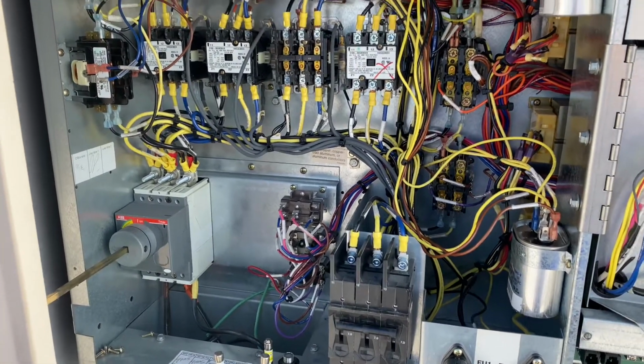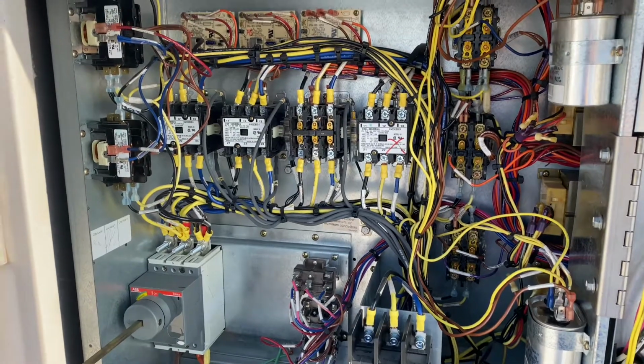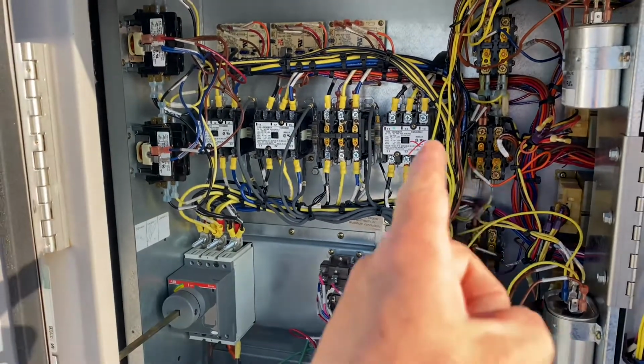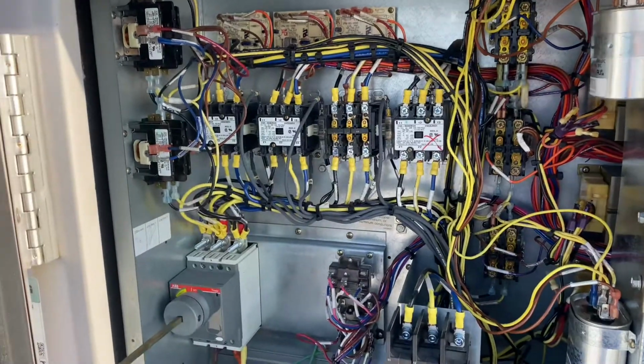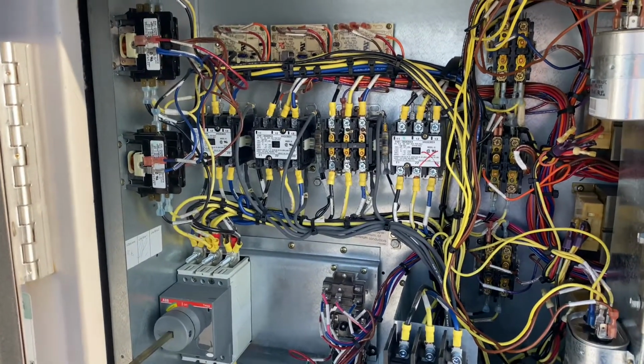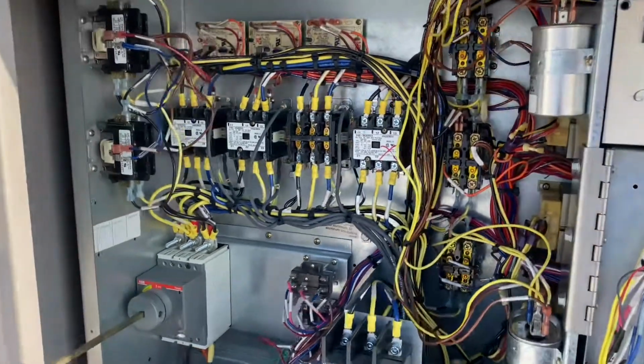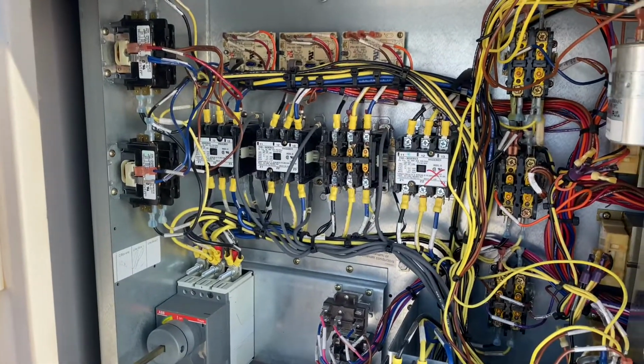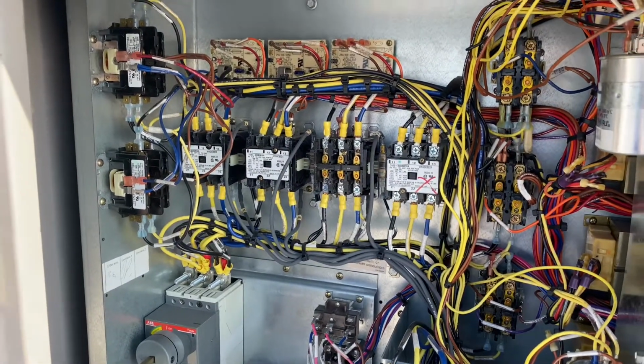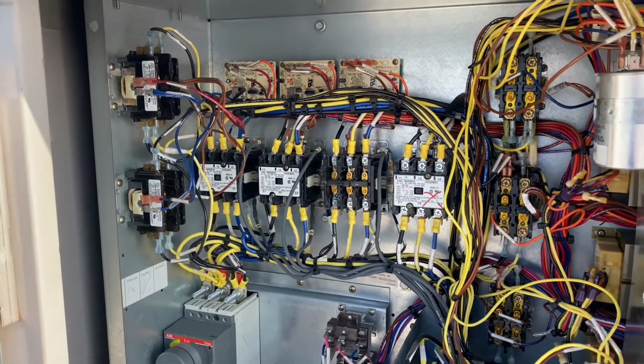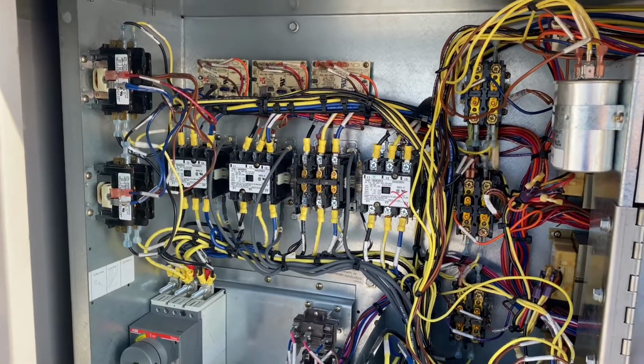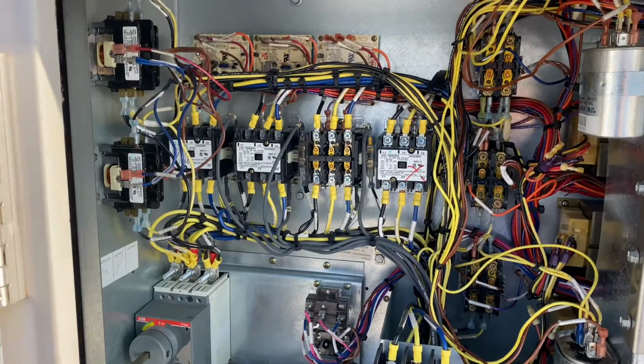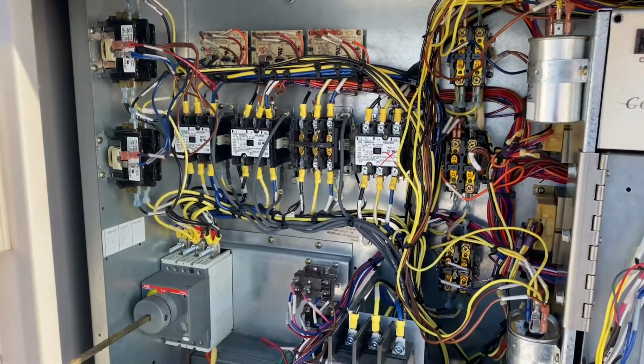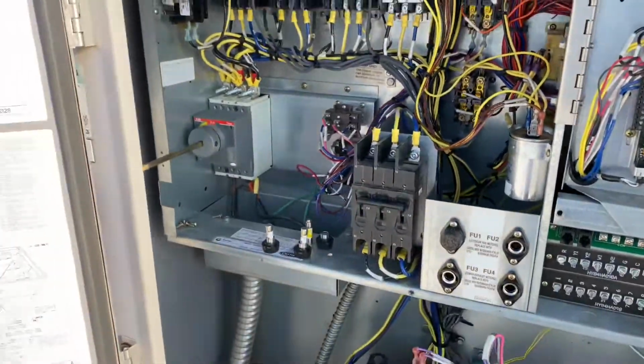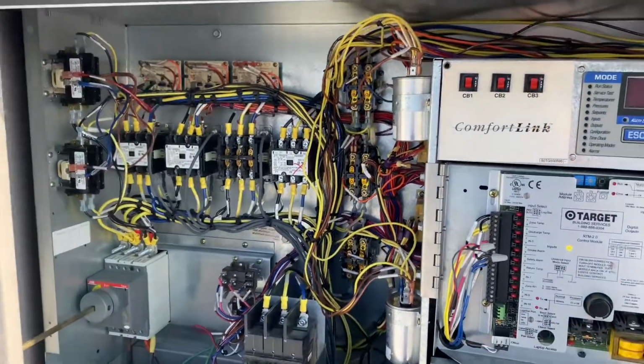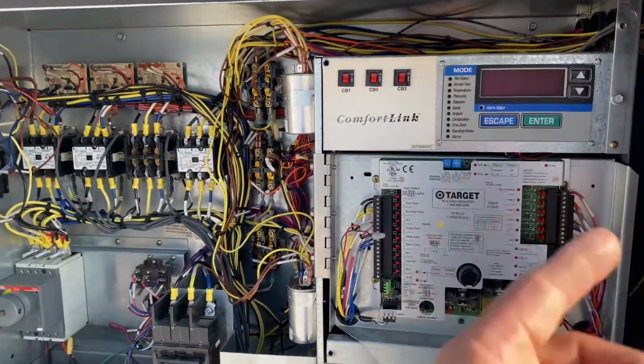So then with an insulated screwdriver, I just quickly cycled the contactors. That word just ran out of my head. Cycled the contactors for the compressors and the blower fan, make sure they turned on, and obviously it didn't trip anything. I didn't see any burn marks or anything, so I knew I was good.